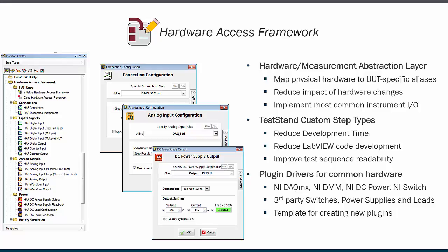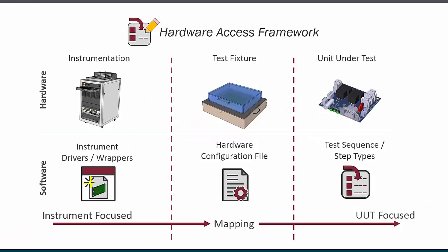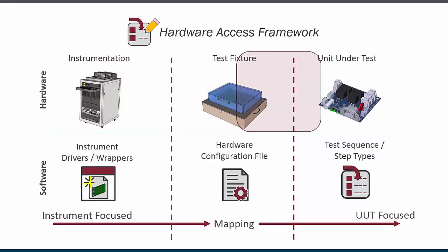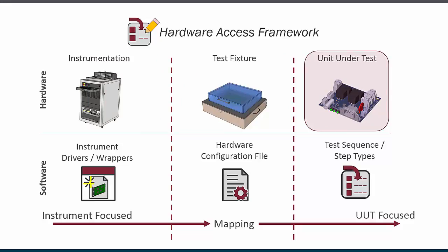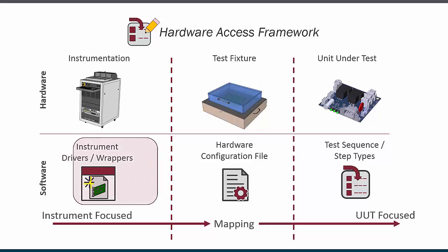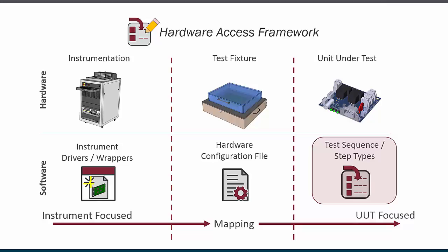These actions are implemented as configuration dialogs in TestStand, rather than requiring direct code calls. This reduces the need for intimate hardware, driver software, and connection knowledge, and provides a standard interface that all test developers can use, regardless of platform-specific instrumentation. Just like when developing automated test hardware, where typically the base system instrumentation is generic and the test fixture maps that instrumentation to the UUT-specific connections, when developing test sequences using the hardware access framework, instrument drivers are generic and the hardware configuration file maps the generic drivers to the test step configurations that are specific to the unit under test.